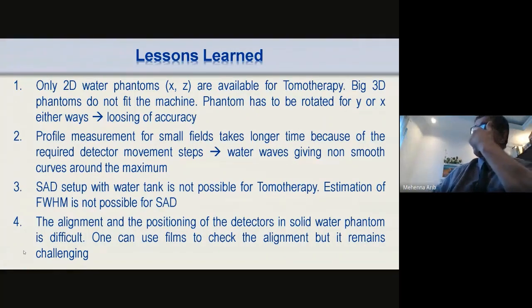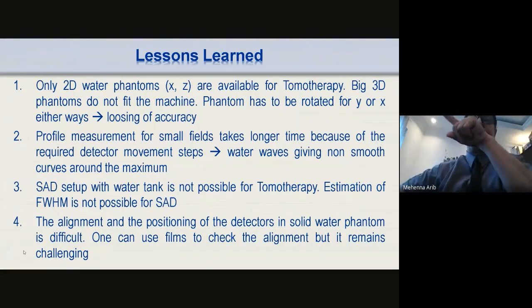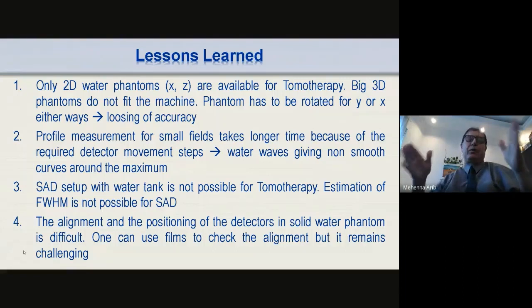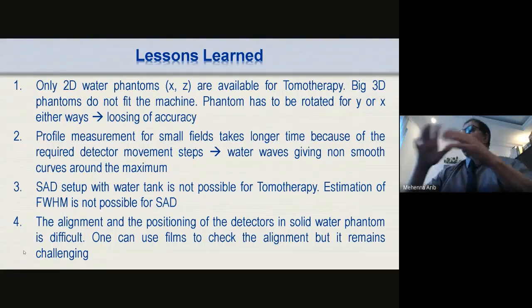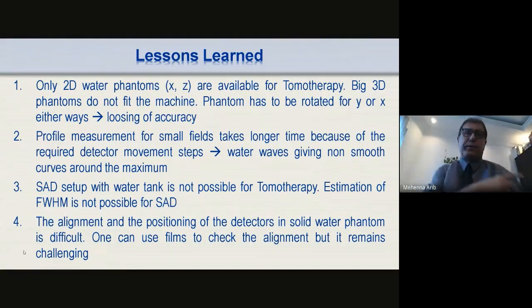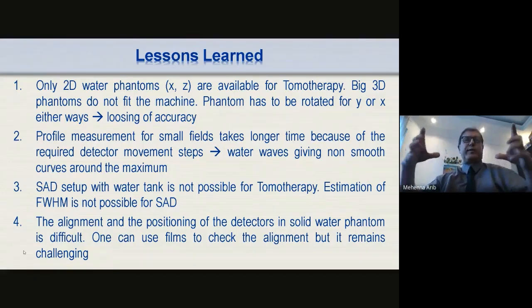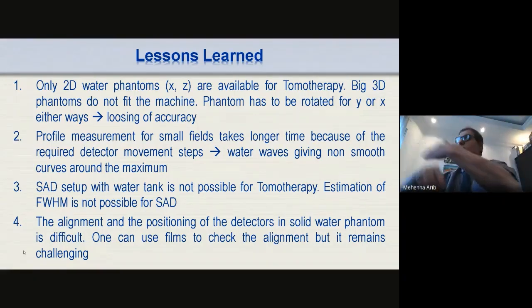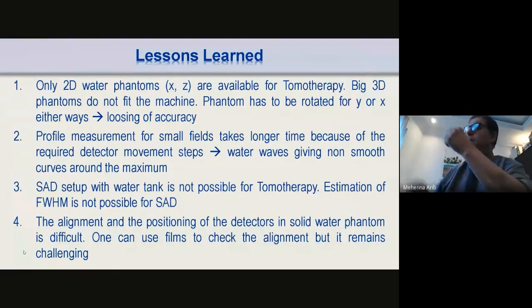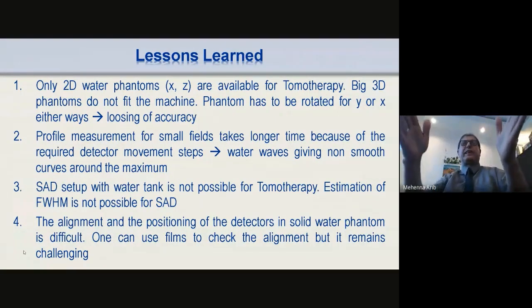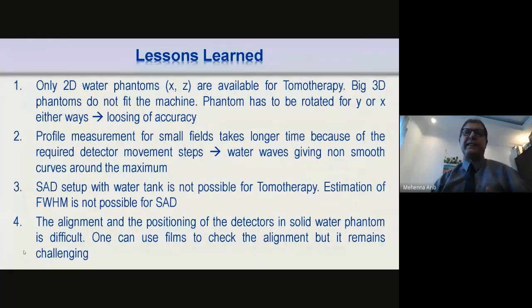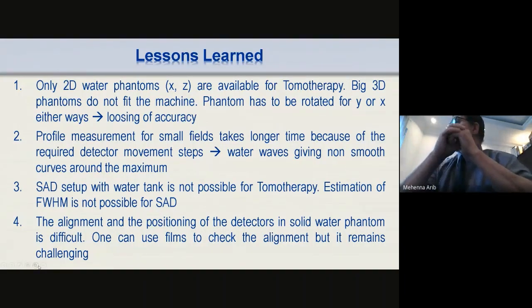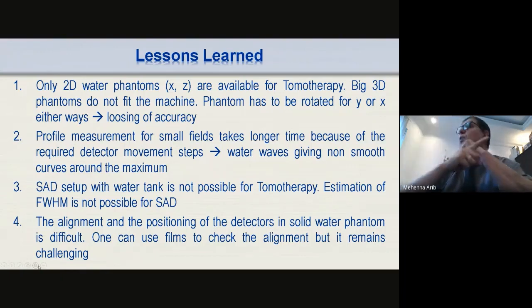First of all, for tomotherapy, we had only a 2D water phantom available, whereas for the LINAC or for the Cyberknife, you can use a 3D phantom, so you can scan in X, Y, and depth dose without any problem. For the tomotherapy, you need to put the phantom in and then remove it, turn it by 90 degrees, and then you lose accuracy because you need to really have the detector centered at the same center. The profile measurement for small fields takes longer because of the required detector movement.